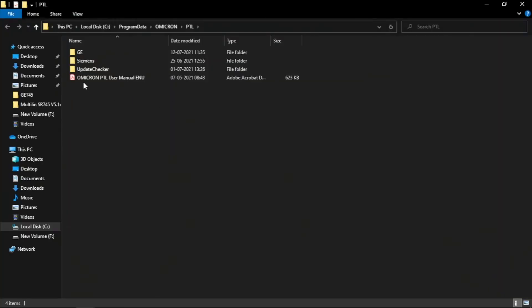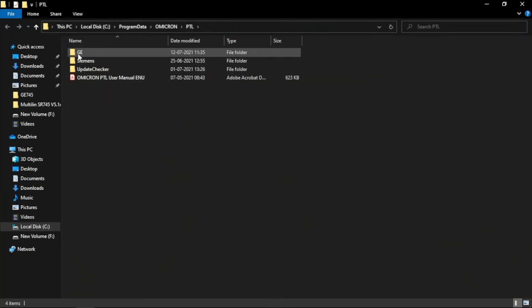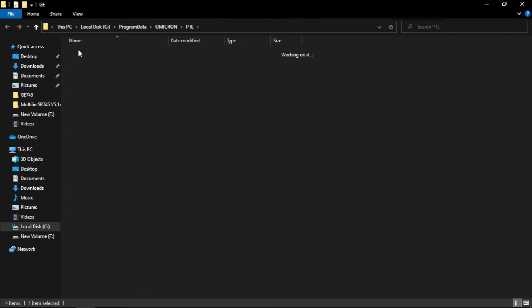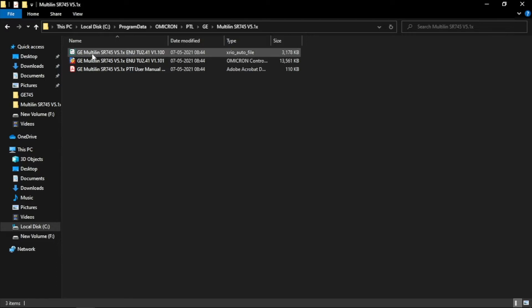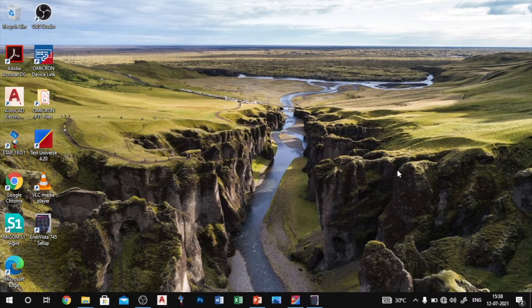Now I check the Omicron PTL file for the GE 745 relay. I already downloaded from the website. Here we have the XRIO file which we can import in the test universe for our relay setting.